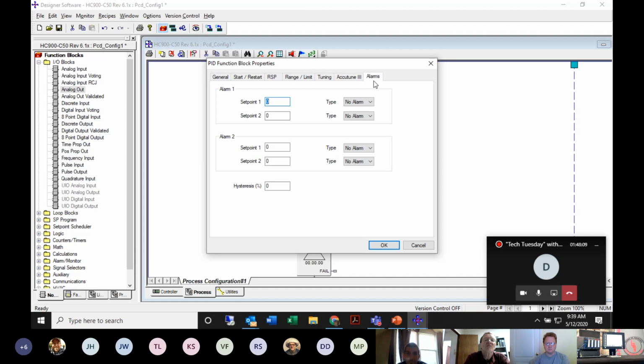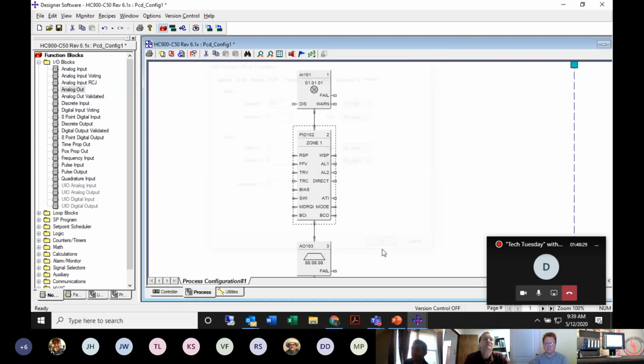Last but not least is alarms. So as before, when we were programming the UDC, you can see that we also get 2 standard alarms with the PID block. We can set our alarm one maybe to 1000 degrees, and maybe I want it to be a PV high alarm. Click OK.